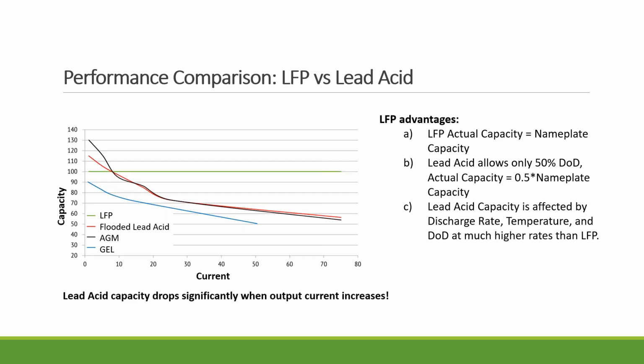Now, another distinction of LFP or lithium batteries in general from the traditional lead acid family is this: if you live in the Caribbean, for example, and you need to turn on your air conditioning, then with lead acid batteries you can suddenly see the battery drain very quickly. You expect it to last 2 hours, and it may turn out to be like 30 minutes. With lithium, you do not have that issue as long as you're operating within the maximum discharging amperage. That capacity will not drop.